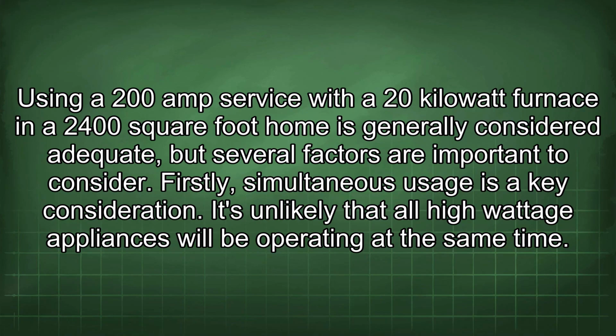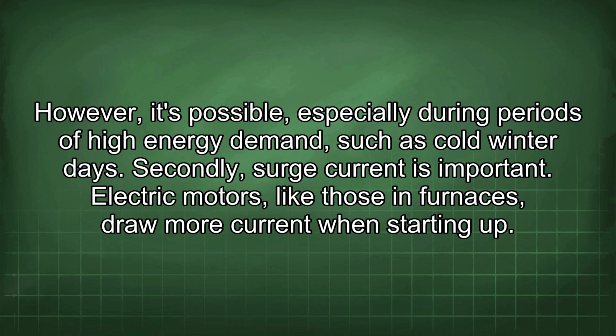Using a 200 amp service with a 20 kilowatt furnace in a 2400 square foot home is generally considered adequate, but several factors are important to consider. Firstly, simultaneous usage is a key consideration. It's unlikely that all high wattage appliances will be operating at the same time. However, it's possible, especially during periods of high energy demand, such as cold winter days.